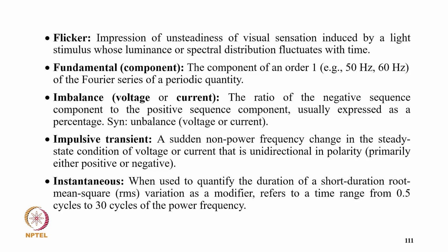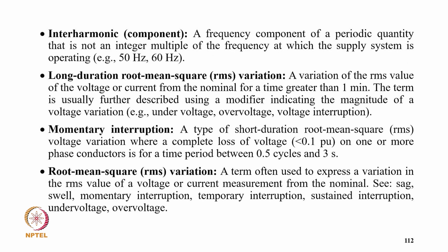Short duration: when used as a modifier, refers to time durations from 0.5 cycle to 30 cycles. Interharmonic component: a frequency component of a periodic quantity that is not an integer multiple of the frequency at which the supply is operating, 50 or 60 Hz. Long duration root mean square variation: a variation of the RMS value of voltage and current from nominal for greater than 1 minute.